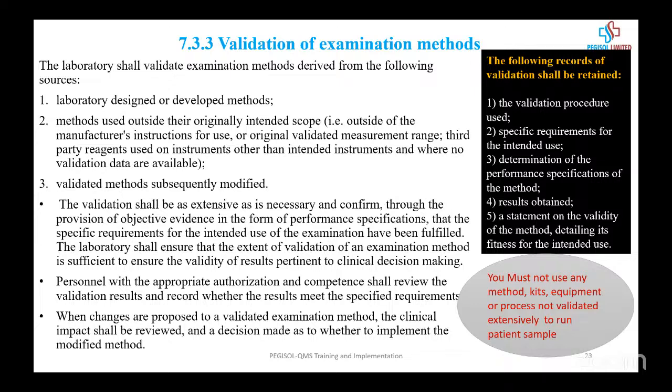Now, let's say there's also an expansion. Or you have been using PCR equipment for COVID testing, and you decide to now start to use that for HIV viral load, or let's say for Lassa fever testing. You can't just buy reagents and just start using it. You have to verify, you have to validate before you start using patient samples.